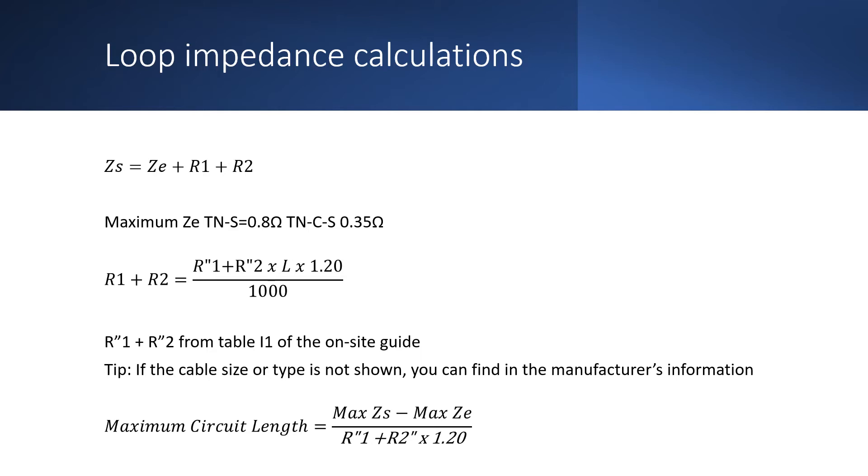There is only one difference to this equation when we're carrying out the circuit length. As you noticed before, we divide by 1000. This is because the values are given in milli-ohms per meter. So when we're carrying out this equation, we have to first divide the tabulated value of R1 and R2 by 1000.